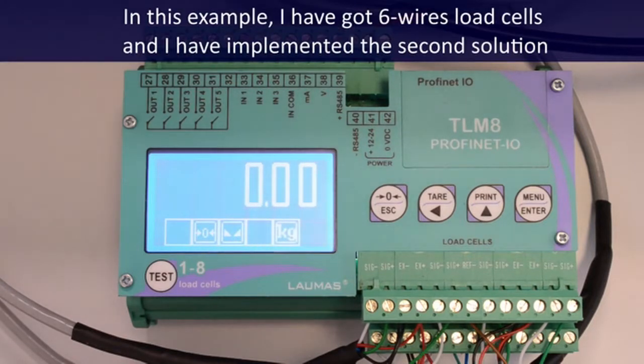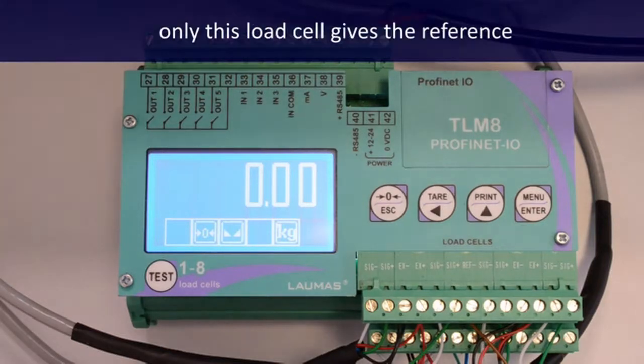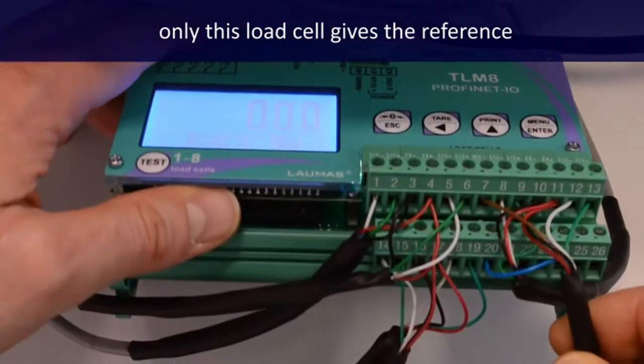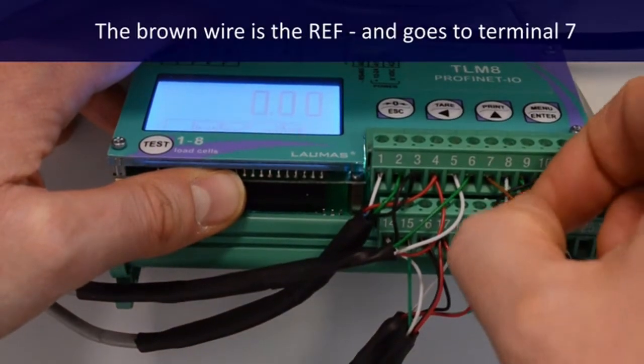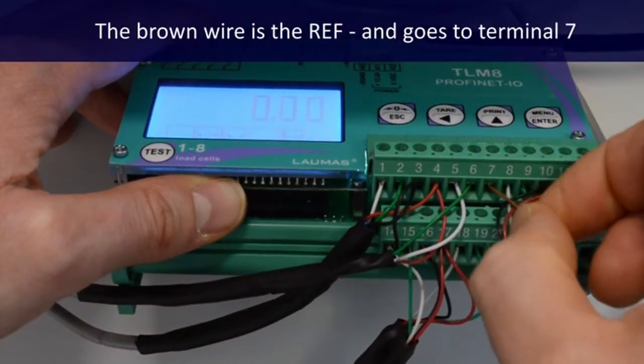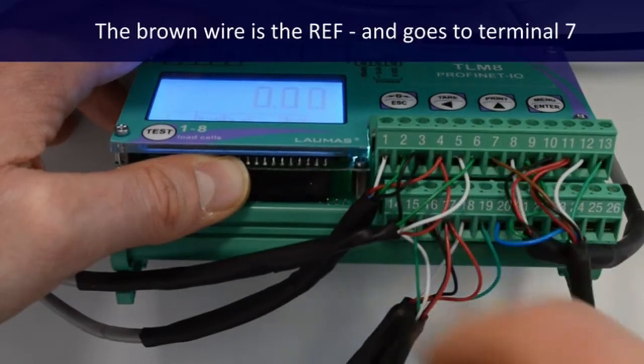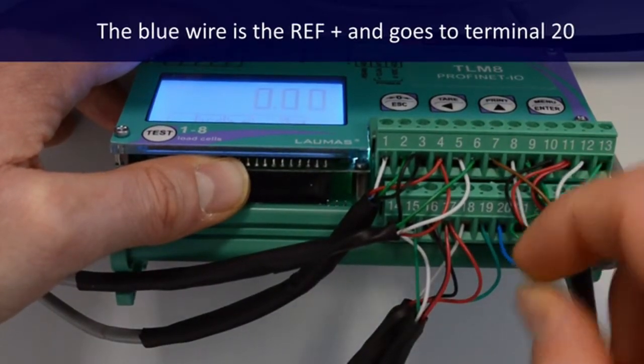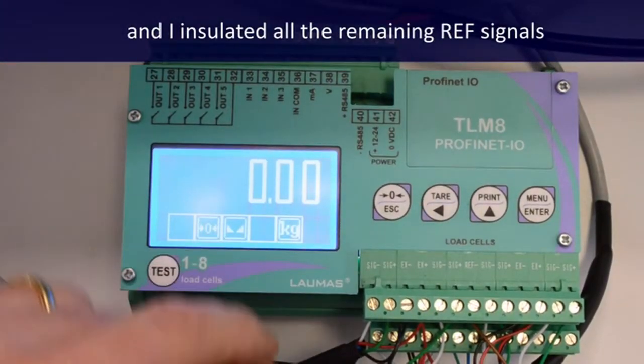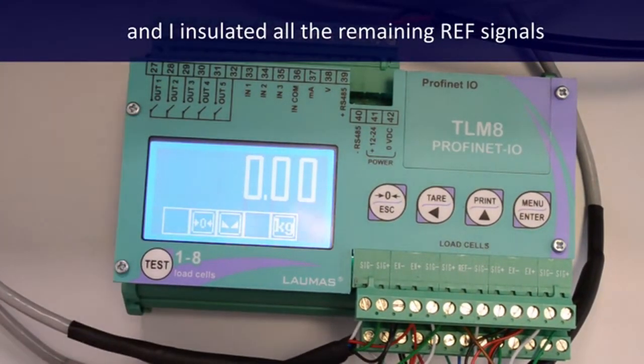In this example, I've got 6-wire load cells, and I have implemented the second solution. Only these load cells give the reference. The brown wire is the ref minus and goes to terminal 7. The blue wire is the ref plus and goes to terminal 20. And I insulated all the remaining ref signals.